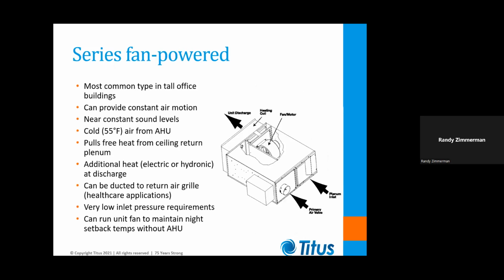If we look at this cutaway of a series fan-powered box, you're going to see that they're pretty much defined by the location of the motor blower inside the unit. You'll see that the motor and blower is located at the discharge of the unit. Then on the inlet panel, you've got a round inlet that's going to take cold air from the air handler, and it's got a flow sensor and a damper in it, just like a single duct VAV box. Then you've got that big rectangular opening there called an induction port, or a plenum inlet, some people call it.